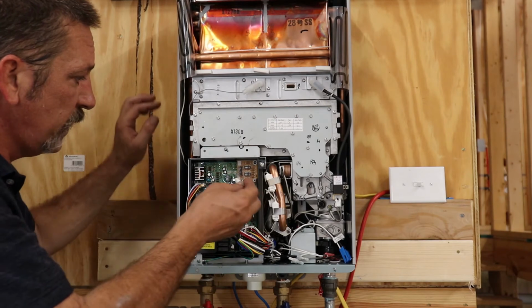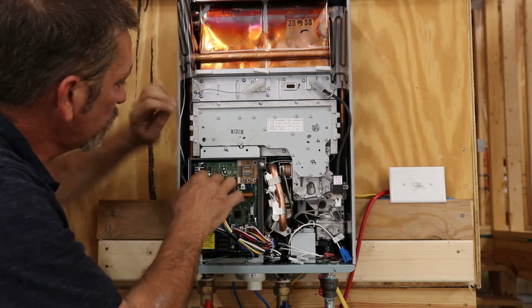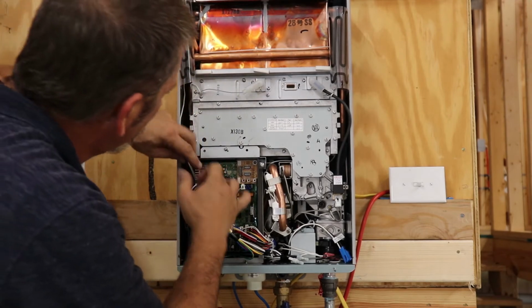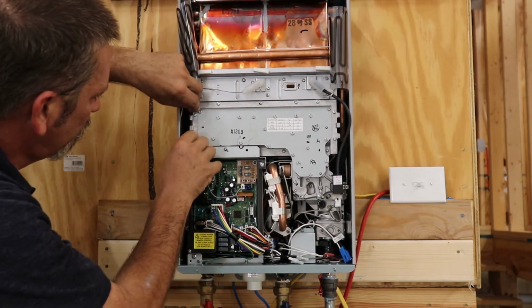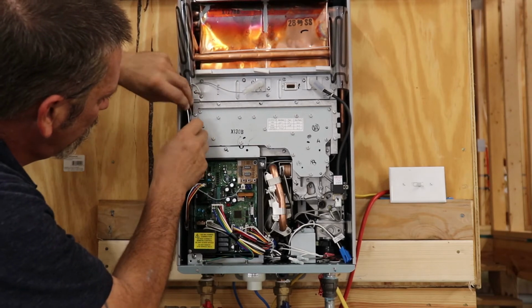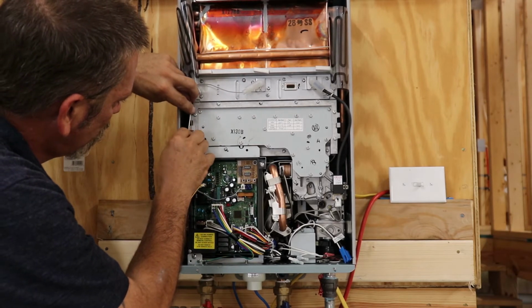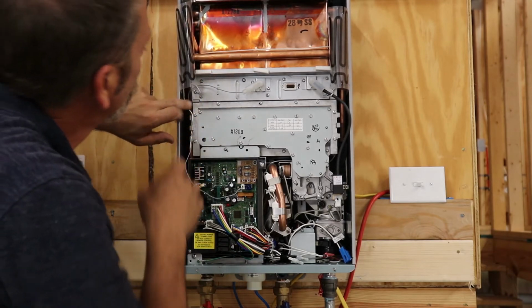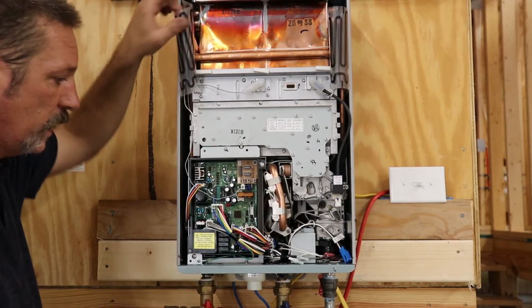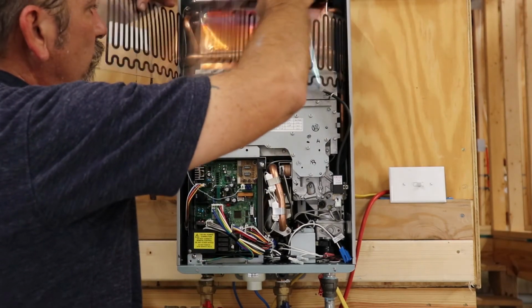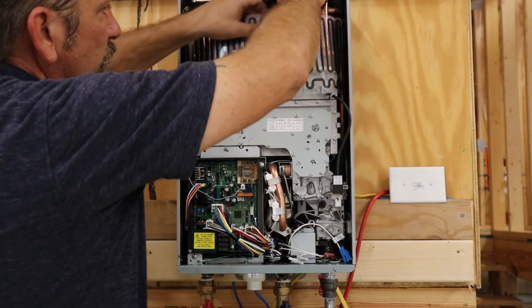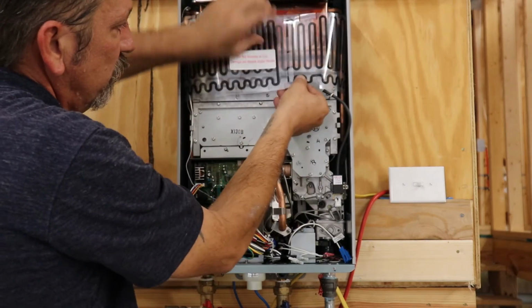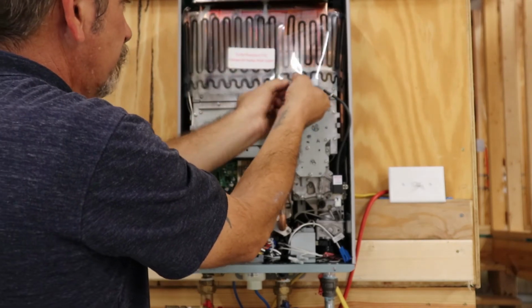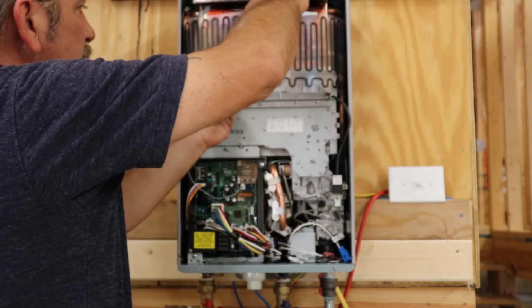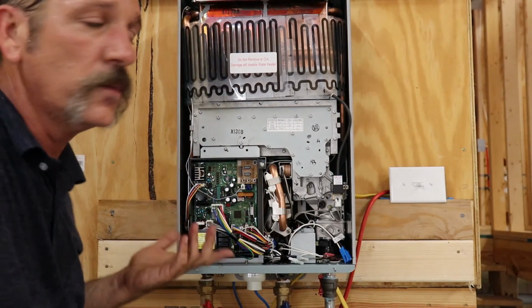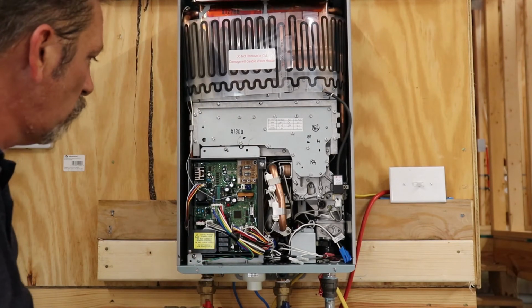Don't forget your flame rod—you took that little white connector off, put it back up in its little cradle. It should go back through these little tabs here, and then your upper thermistor, which is this thing up here sensing temperature. Be really careful with that thermal protection, tuck it back in, put these little tabs back. This stuff is pretty flexible, but just be careful with it—don't tear it, don't rip it, because if you do, your water heater's not any good anymore.